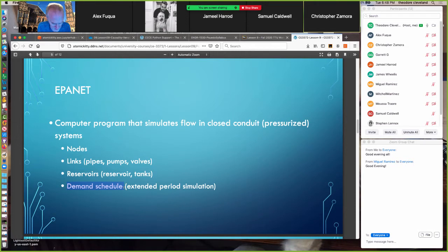And when that's invoked, what the program is doing is the hydraulics are done at steady flow. So any change in flow rate anywhere in the system, the hydraulics is changed instantly as far as the pressure computations are concerned.